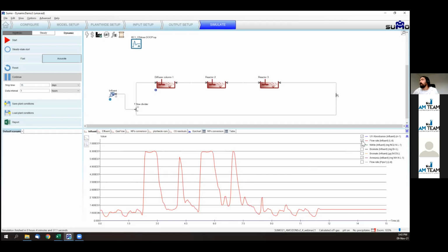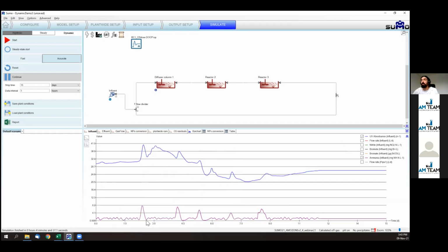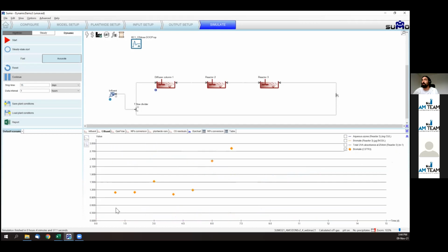And right after that, there is a dip in ammonia as well, due to the upstream biological plant, which is probably over aerating as a response to the ammonia controller, and also at this other peak, ammonia is lacking.